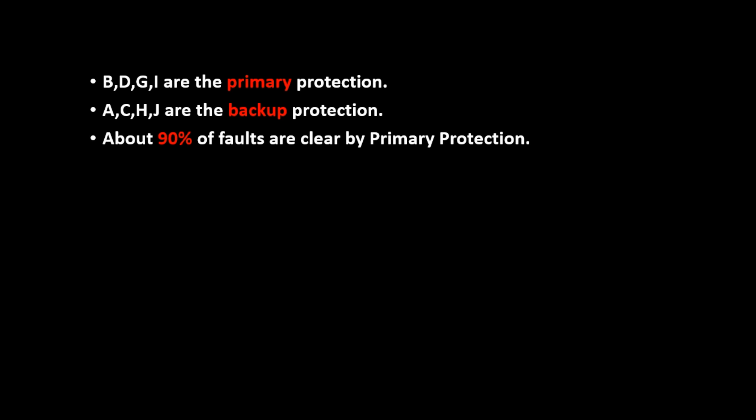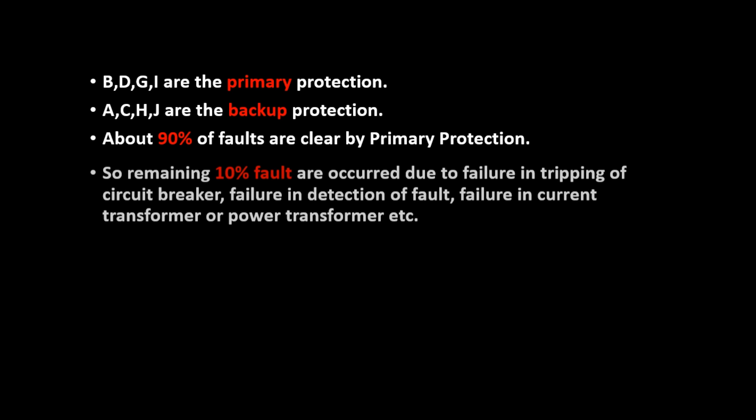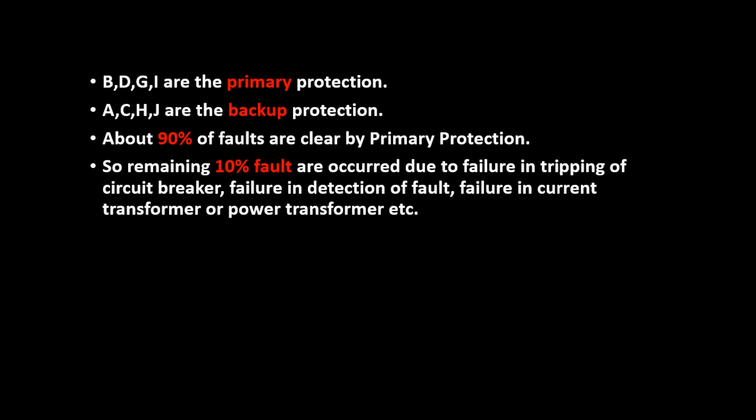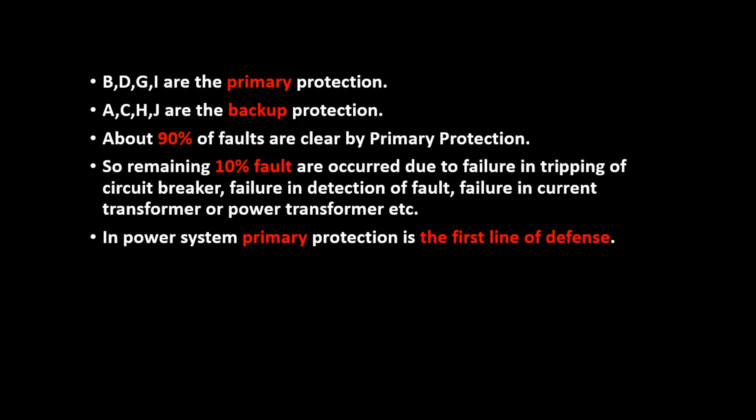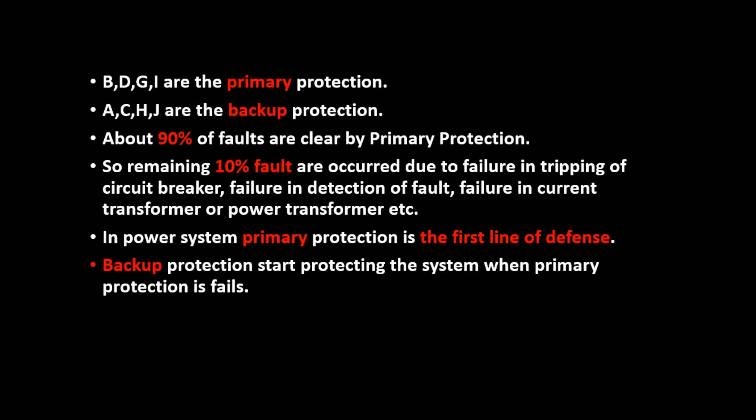About 90% of faults are cleared by primary protection. The remaining 10% of faults occur due to failure in tripping of circuit breaker, failure in detection of fault, or failure in current transformer or power transformer. In a power system, primary protection is the first line of defense. Backup protection starts protecting the system when primary protection fails, clearing that remaining 10% of faults.